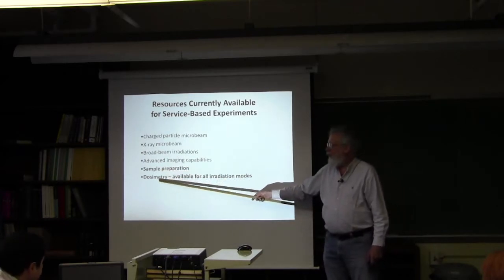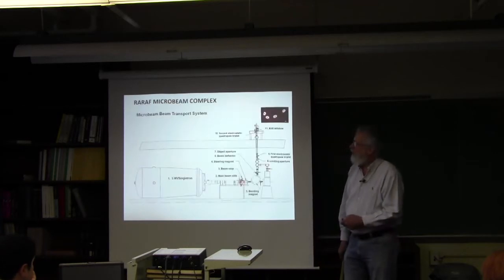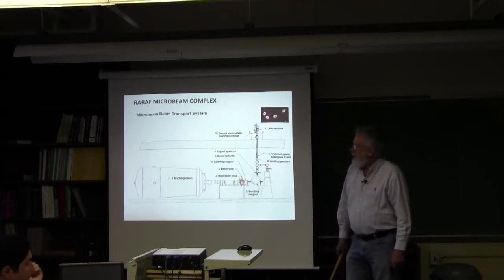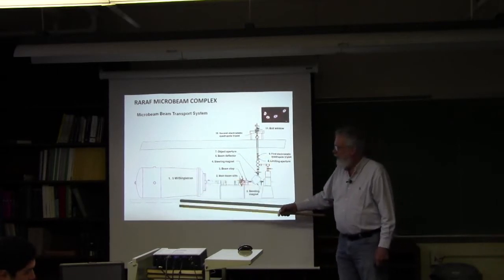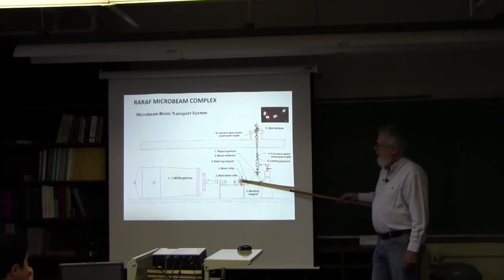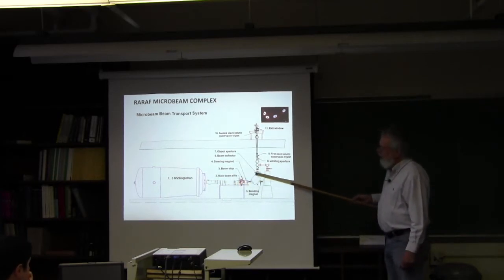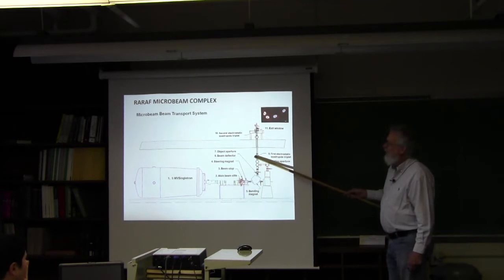The microbeam transport itself has the singletron, a beam line, beam defining slits here, a 90 degree magnet. The object aperture is located just above that. The limiting aperture is located just before the first electrostatic triplet.